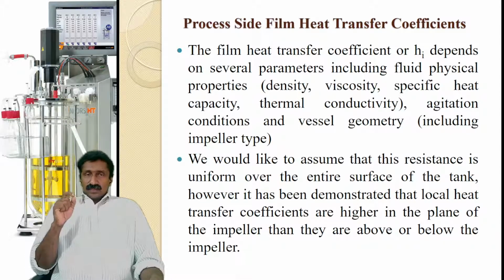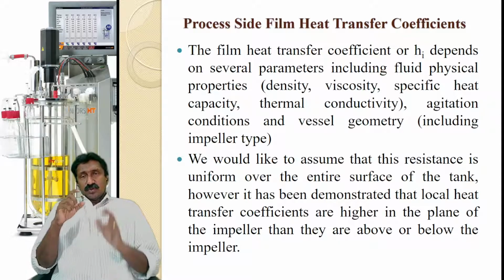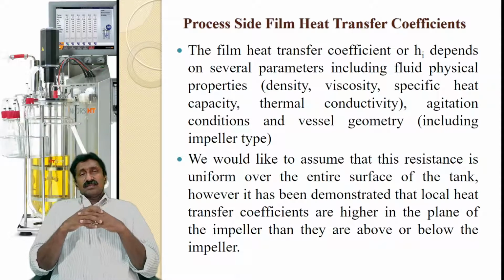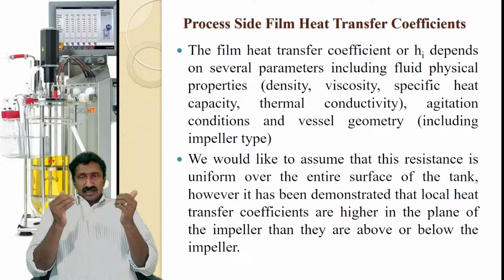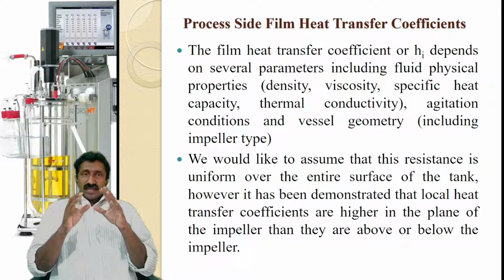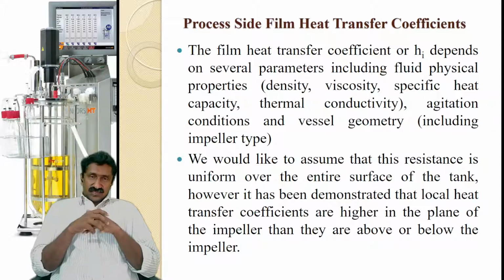Okay. Now, we would like to assume that this resistance is uniform over the entire surface of the tank. However, it has been demonstrated that local heat transfer coefficients are higher in the plane of the impeller than they are above or below the impeller. So, as I mentioned, there will be localized differences in the heat transfer efficiency.